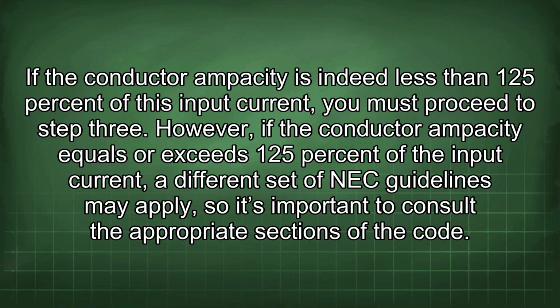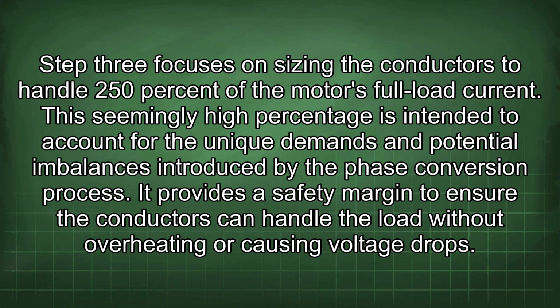However, if the conductor ampacity equals or exceeds 125% of the input current, a different set of NEC guidelines may apply, so it's important to consult the appropriate sections of the code. Step 3 focuses on sizing the conductors to handle 250% of the motor's full load current. This seemingly high percentage is intended to account for the unique demands and potential imbalances introduced by the phase conversion process. It provides a safety margin to ensure the conductors can handle the load without overheating or causing voltage drops.